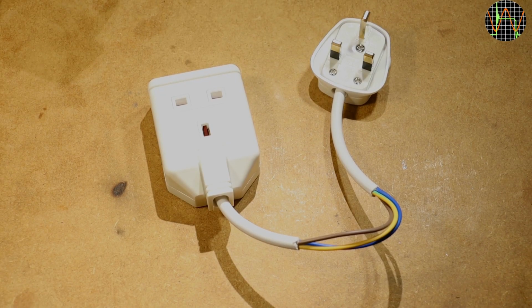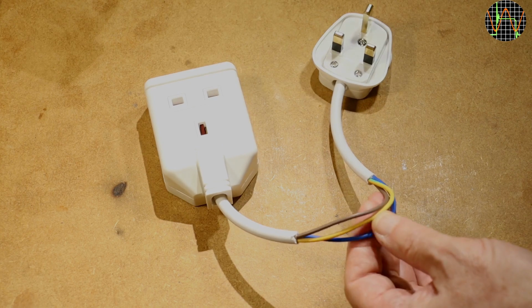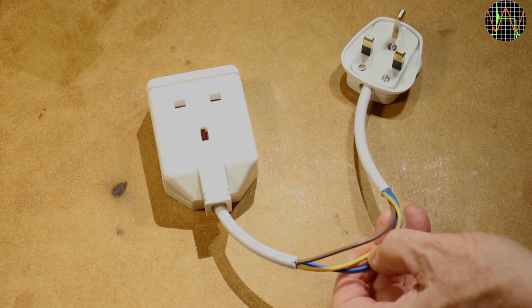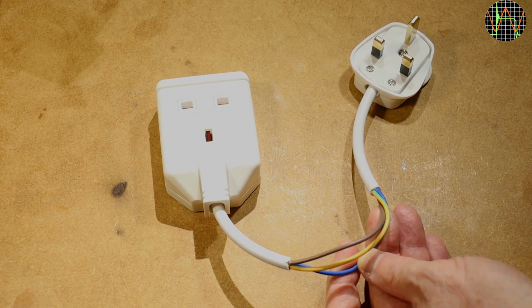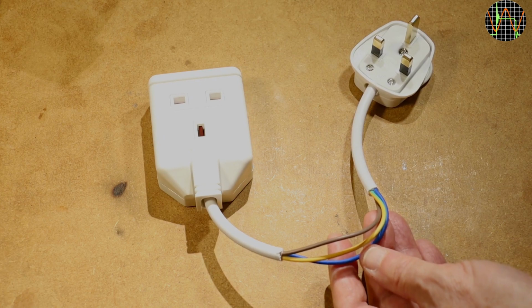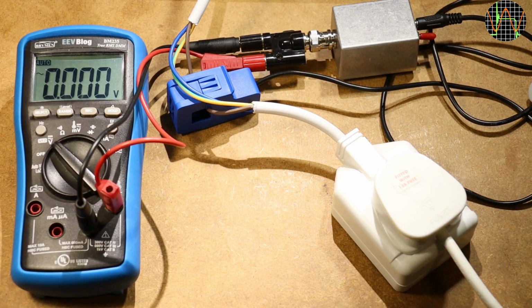And speaking of measuring mains, with a current transformer or clamp meter available, you should make yourself an extension cable like this, where you can clamp each wire separately. Here I am using it to clamp the live wire and measure the current of a fan heater in times 10 mode. First, only the fan motor is running and we can see about 200 milliamps. With the first heating element on, that jumps to 4.3 amps and then to 8.2 amps with the second one on in addition.